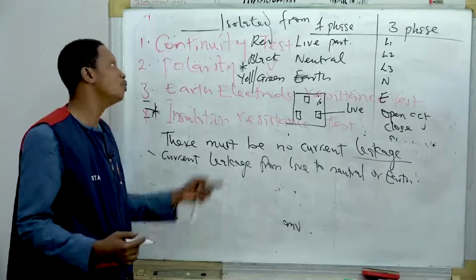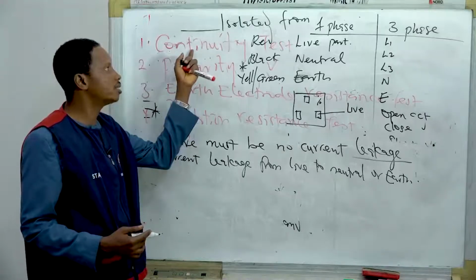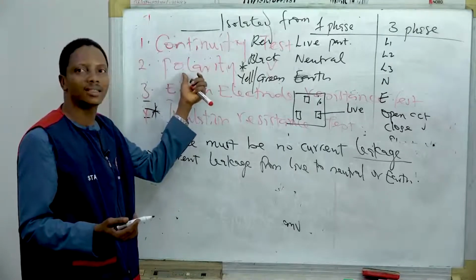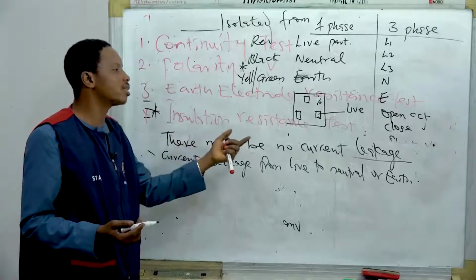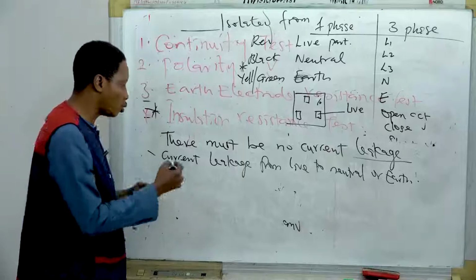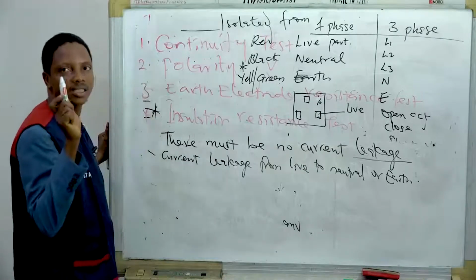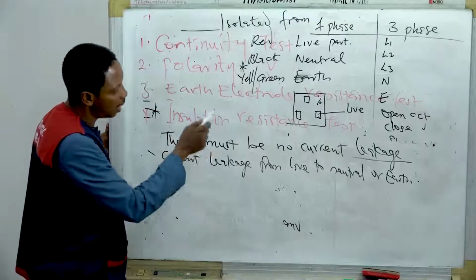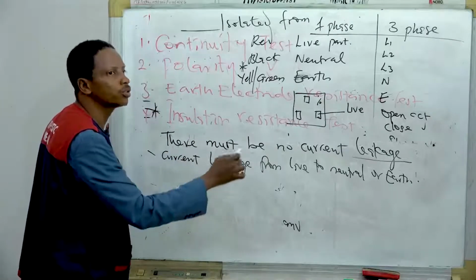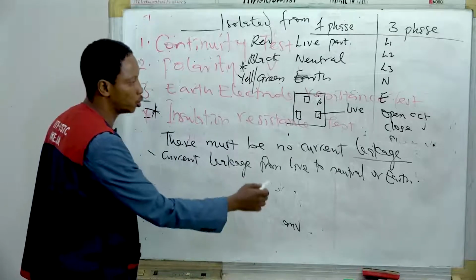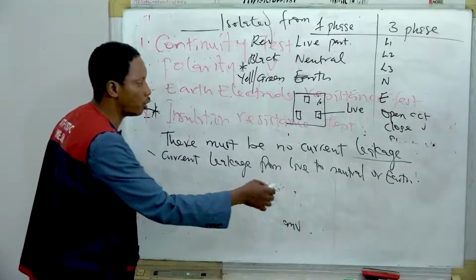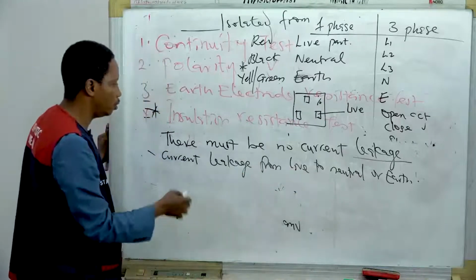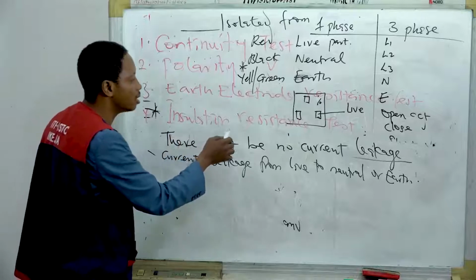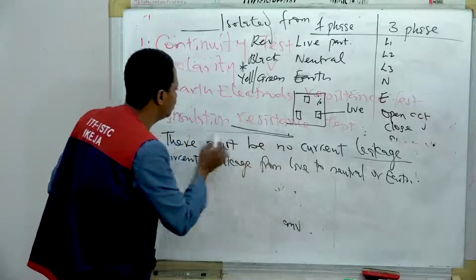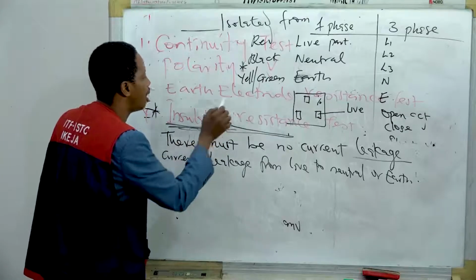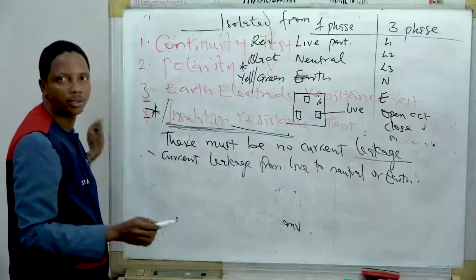So, we carry out insulation resistance test. We also use the same continuity test. I said continuity test is very key. We use it for polarity test. Now, we are talking about insulation resistance test. We are also using what? Continuity test to confirm current leakage. It must not exist. So, line 1, the live conductor, must not have a link to the neutral conductor, and it must not have any link to the earth conductor. That is why you carry out insulation resistance test. And how can we have a link? When the insulation has broken down. So there will be leakage.